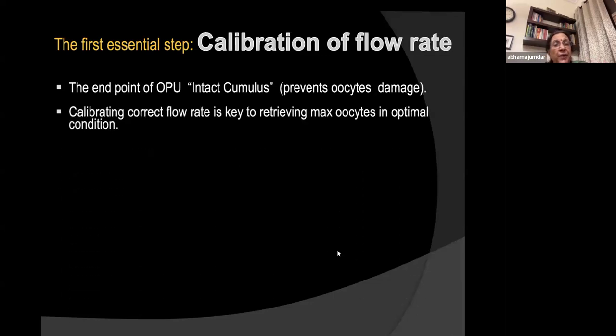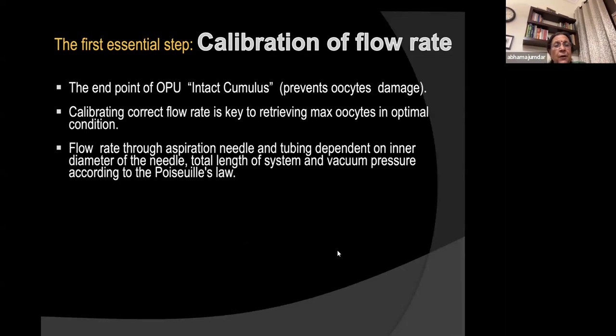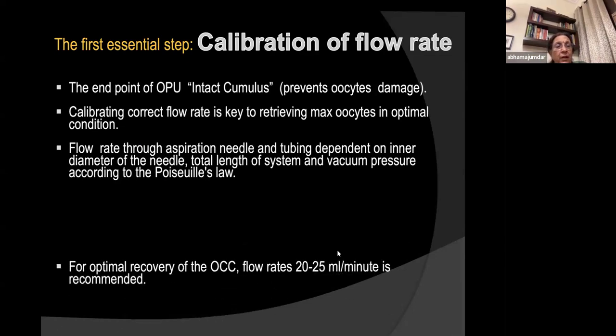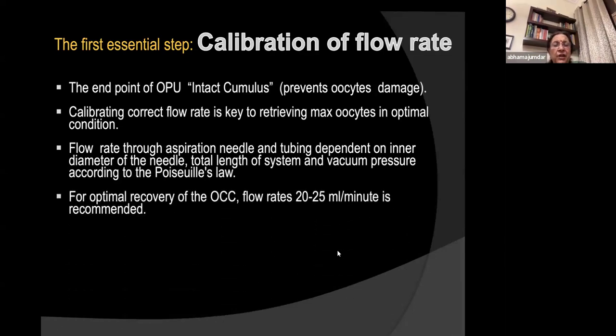Then how do we calibrate the correct flow rate? That is the key to retrieving maximum oocytes in optimal condition. Flow rate through the aspiration needle and tubing is dependent on the inner diameter of the needle, total length of the system, and vacuum pressure, according to Poiseuille's law. And for optimal recovery of the oocyte cumulus complex, a flow rate of 20 to 25 ml per minute is recommended.